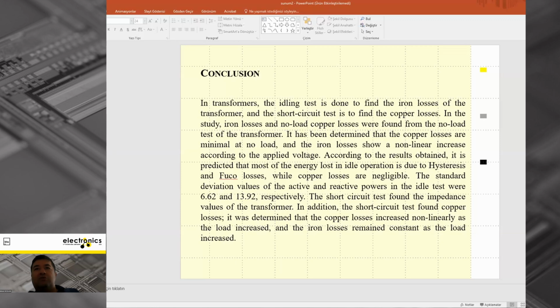The standard deviation values of the active and reactive power in the idle test were 6.62 and 13.92 respectively. The short circuit test found the impedance value of the transformer. In addition, the short circuit test found copper losses. It was determined that the copper losses increased non-linearly as the load increased, and the iron losses remained constant as the load increased, because iron loss depends on the voltage.